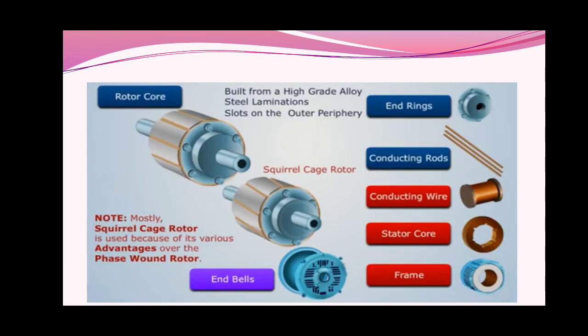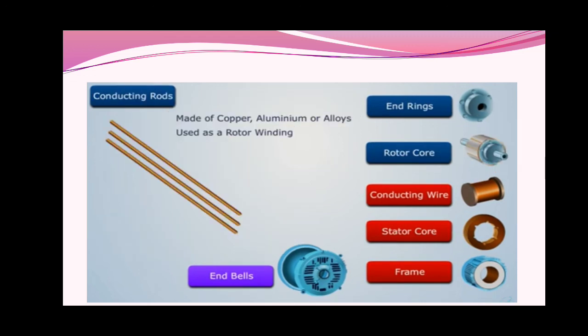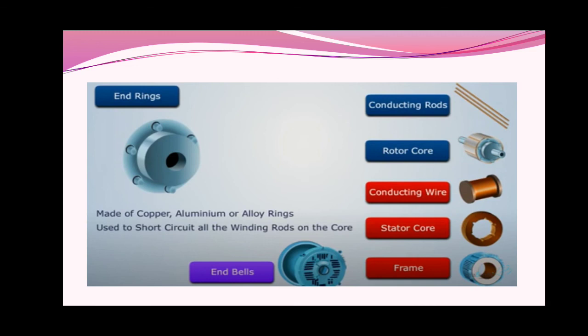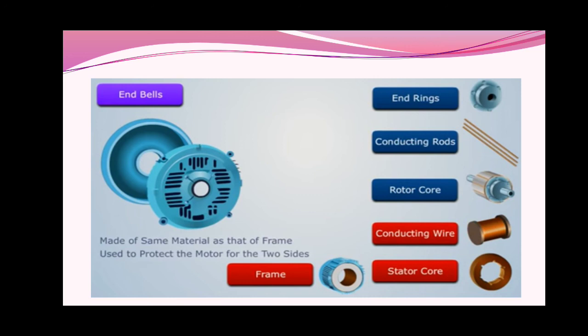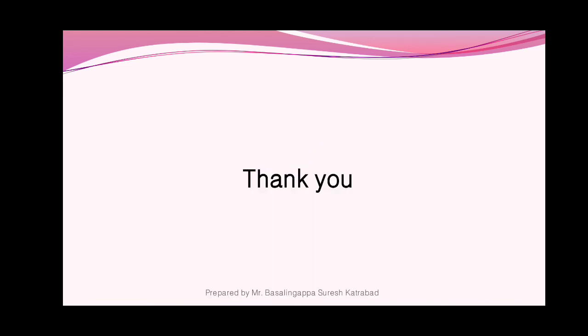Next, the rotor: the rotor core is built from high-grade alloy steel laminations, slotted on the outer periphery — in the stator it is the inner periphery, but in the rotor it is the outer periphery. Most squirrel cage rotors are used because of various advantages over the phase-wound rotor. Conducting rods made of copper, aluminum, or alloy are used as rotor winding. End rings made of copper, aluminum, or alloy are used to short-circuit all the winding rods on the core. End shields are made of the same material as the frame and are used to protect the motor on the two sides. Thank you.